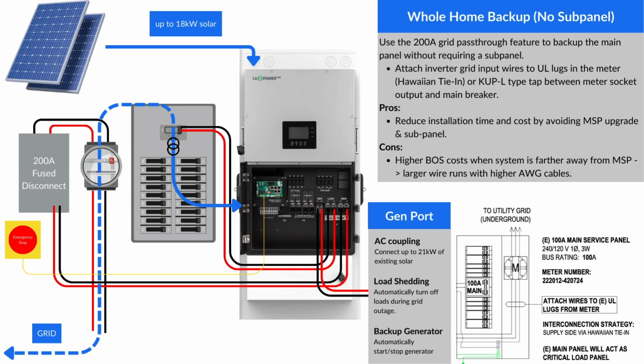Since you will be using thicker gauge high ampacity wires, this works best when you can place PowerStation Pro closer to the panel, as it will help reduce installation cost. In this installation, you will need to get to the wires between the meter and the main breaker. You can do this by unlocking the meter and removing the wires from the UL listed lugs. From the installers we work with, I have been told that this is called the Hawaiian tie-in. Another option is supply tap using a piercing copper connector.